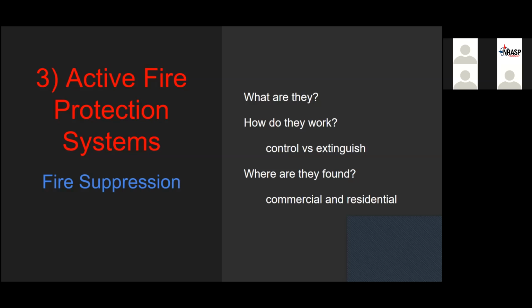It's important that you know if you have a fire suppression system in your building and understand how they work. Some fire suppression systems are designed only to control the fire. So it's going to maintain that fire in a small state until the fire department arrives, and then we are going to continue to put that fire out the rest of the way. Some systems are actually designed to extinguish the fire. This would be like a commercial kitchen suppression system. They are designed to actually extinguish that fire.